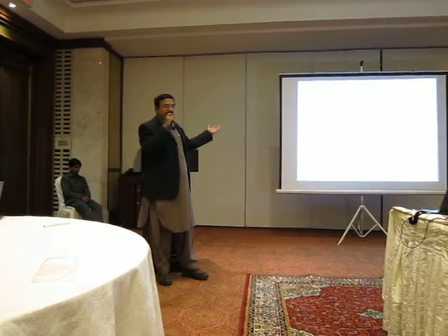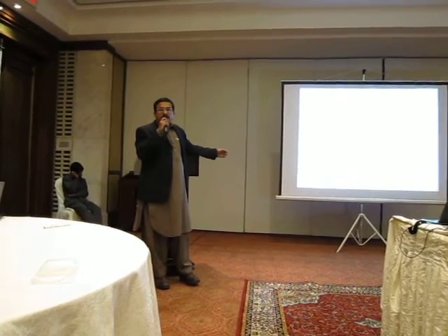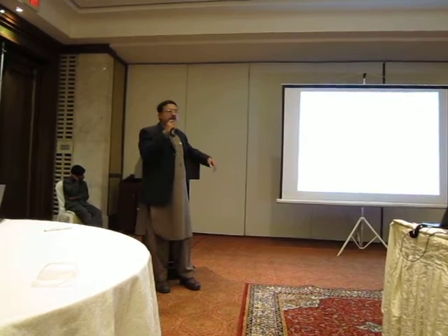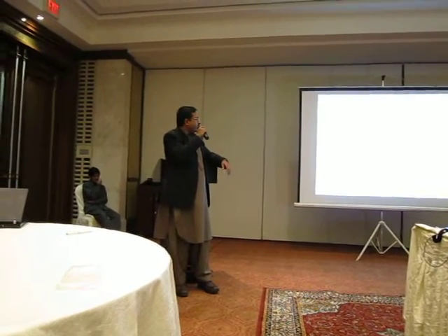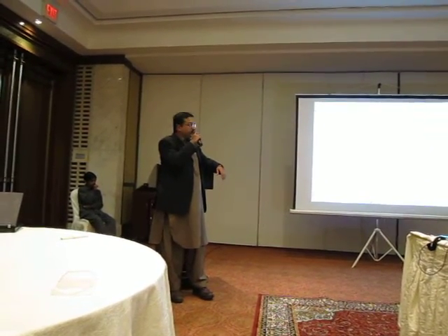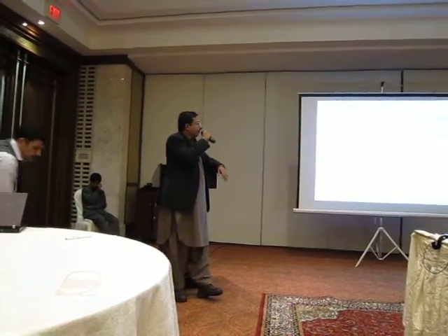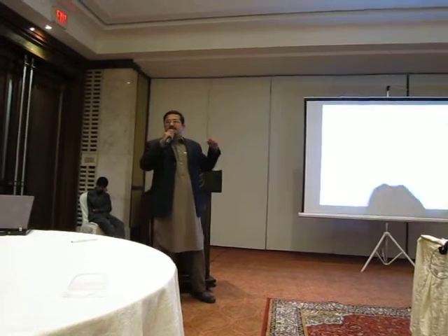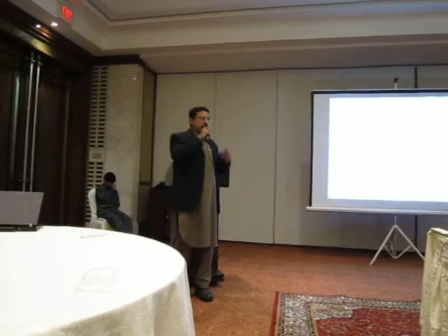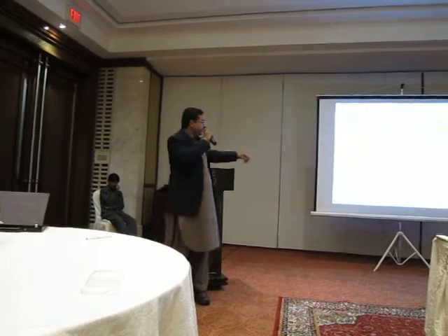The turbidity removal efficiency ranges from 90 to 98%, depending upon the feed water turbidity which is feeding these water filtration galleries. It is also helpful in removing iron and manganese. And for removal efficiency of arsenic, because DI Khan is highly contaminated and there is an arsenic survey of the area, some of the expertise of Sajjad Khan, Zulfi Bhai and Nisar will be helpful in this.